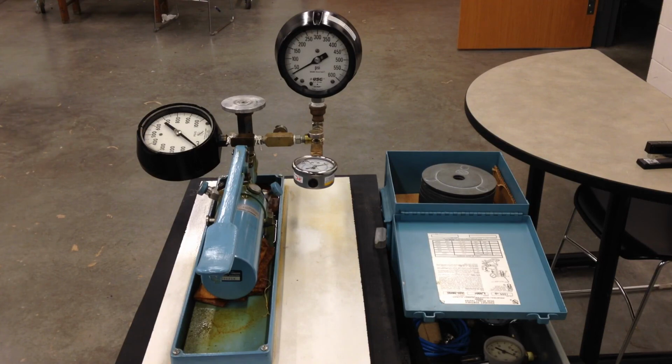And once you've done those correlations, then you can actually compare them. They should be ideally linear. I will stick with linear correlations for all of these. And so when you're done, you will be able to make some kind of determination of how accurate you think these gauges really are, not just from an eyeball standpoint, but from a statistical standpoint.